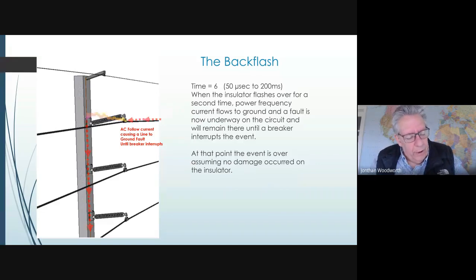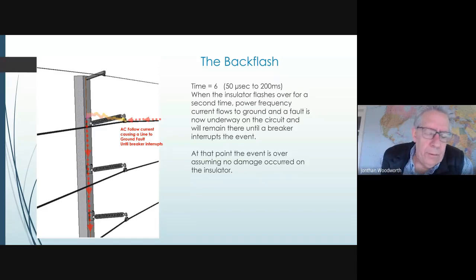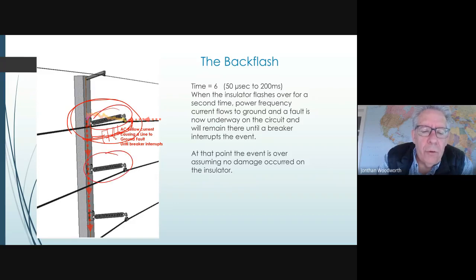And when you have an outage on a transmission line, it doesn't affect one or two people. It usually affects 1 million or 500,000 or 250,000, depending on how big the transmission line is. So one of the ways of protecting power systems is to put an arrester in parallel with these insulators to keep these insulators from flashing over when lightning strikes the system.